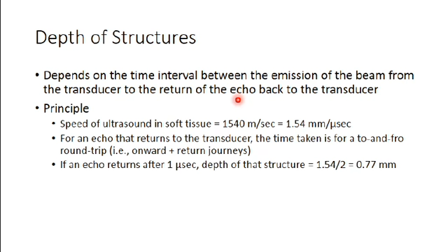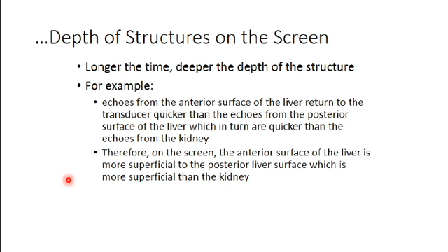So the longer the time it takes for a returning echo, the deeper the depth of the structure. For example, echoes from the anterior surface of the liver will return to the transducer quicker than the echoes from the posterior surface of the liver. Okay, and the echoes from the posterior surface of the liver are quicker than the echoes from the kidney. That's how the computer is able to say, this is the anterior surface of the liver, this is the posterior surface of the liver, and this is the kidney deep to it. Okay, and therefore that's how it depicts it on the screen.